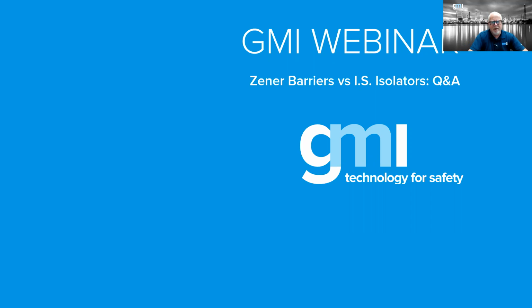In that case, the junction box typically used is an EXE enclosure. The requirement states the box must be certified to meet 60079-0 and must be labeled as containing intrinsically safe circuits. That's why people typically use an EXE box and put a blue label on it stating this enclosure contains intrinsically safe terminals.